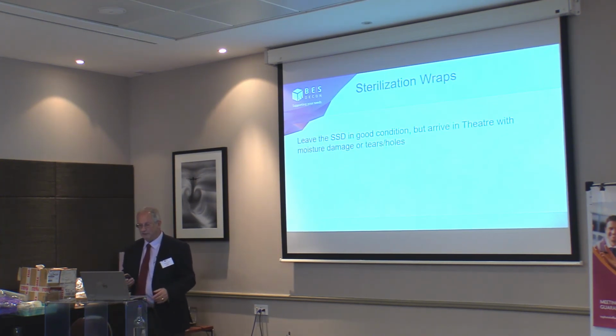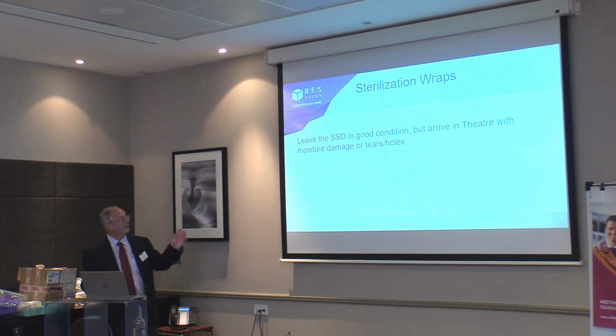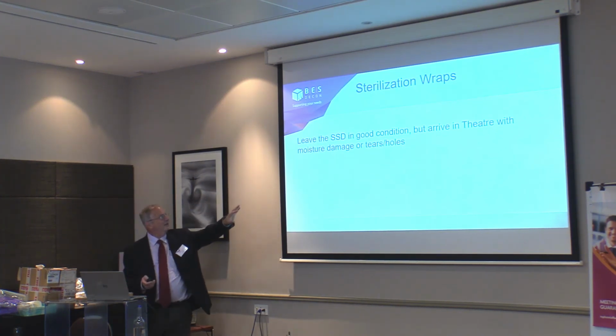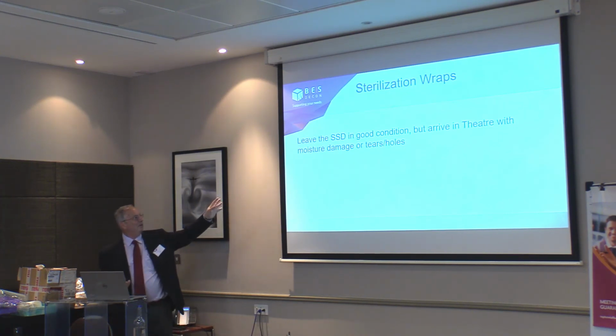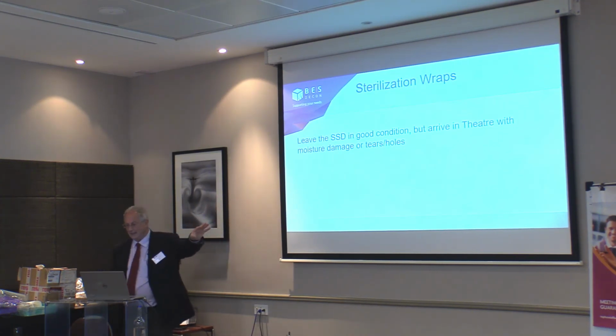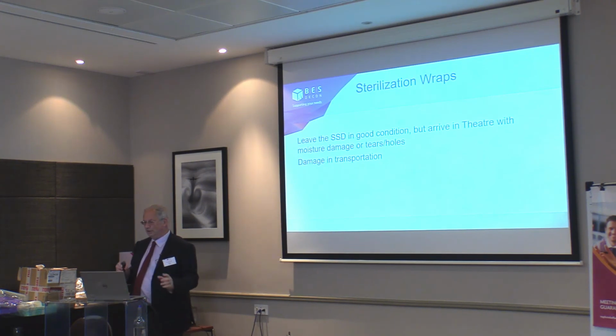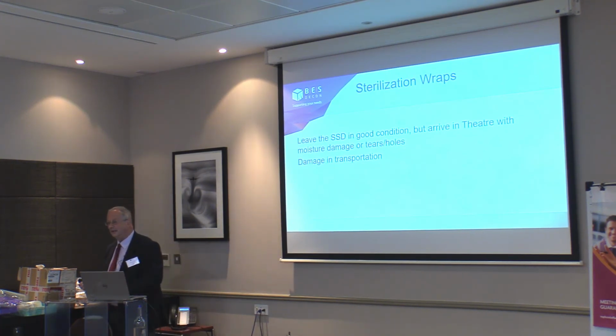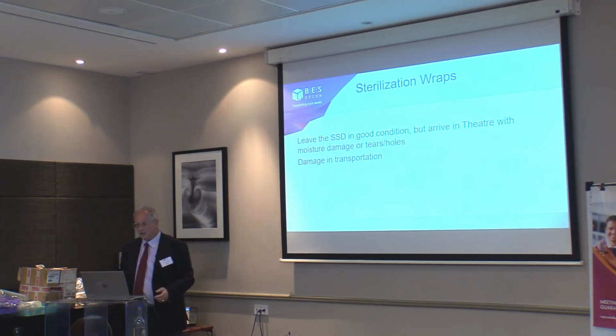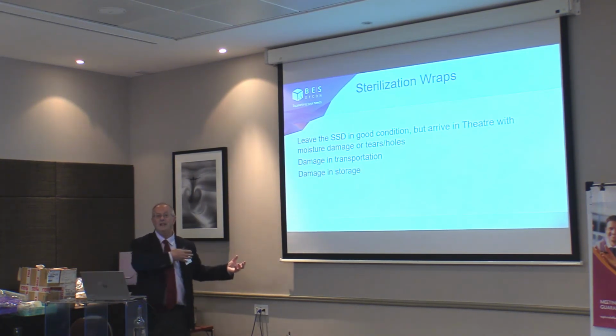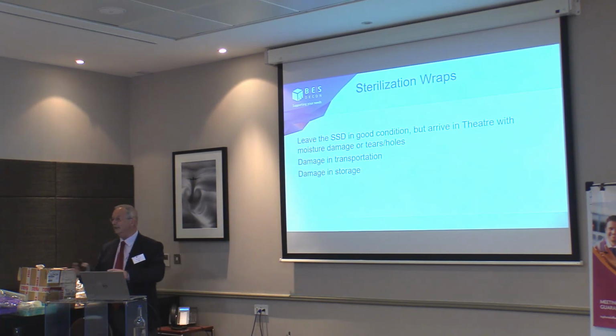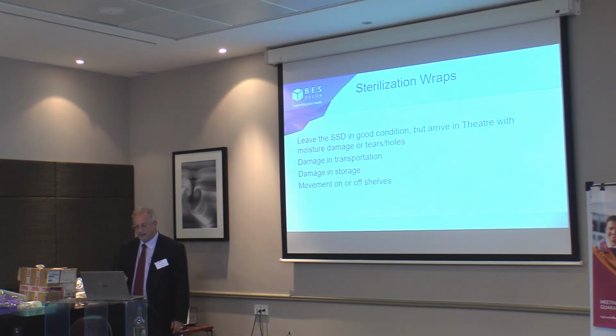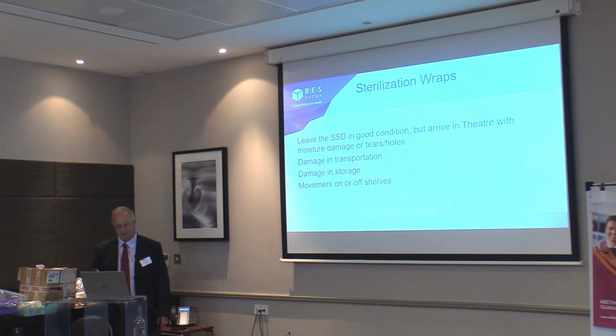And finally, we talk about sterilization wraps. We all know they leave the SSD in good condition, but arrive in theatre with moisture damage or tears and holes. This usually is due to damage in transportation, so people are not carrying them around as they should do, or damage in storage where people will be hauling them on and off shelves in a way that's not really very good for the materials. So it's the movement on or off the shelves that is causing the problems.